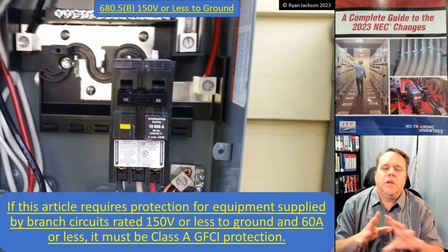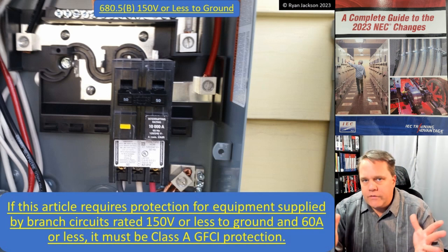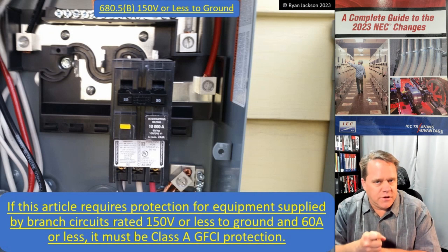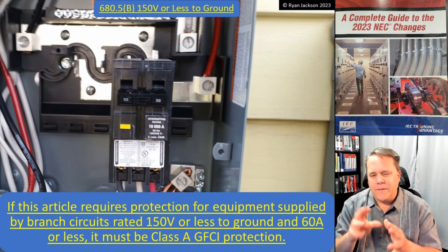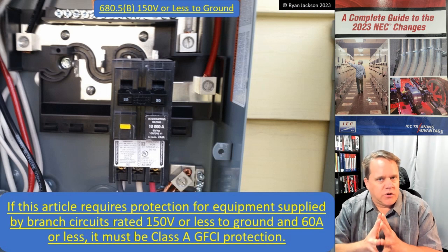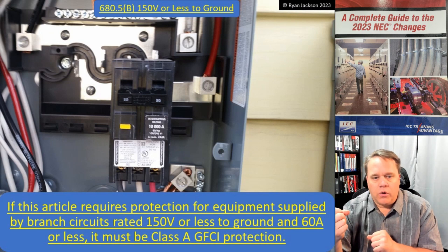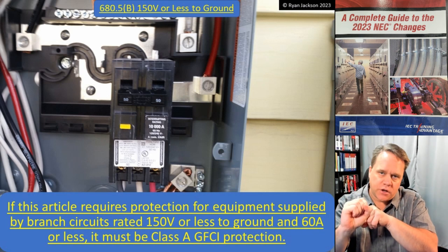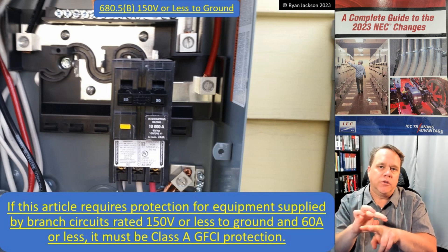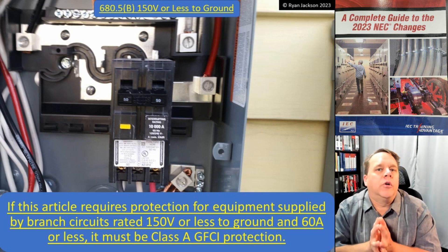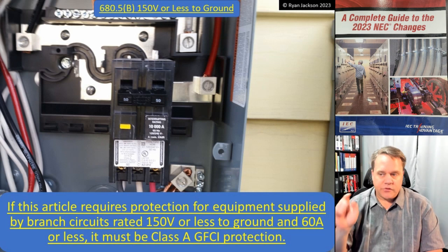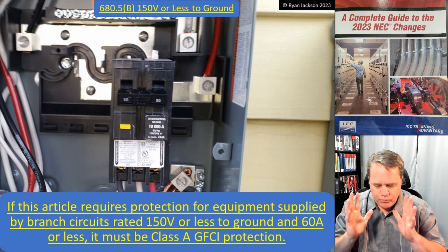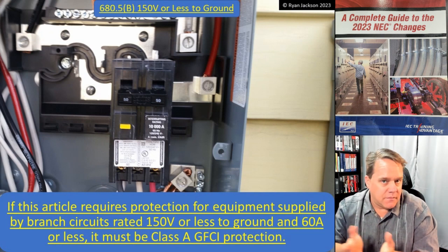GFCIs come in a few different flavors. A Class A GFCI is what we all have in our houses and at commercial buildings. Class A GFCI protection operates between four and six milliamps of leakage current. The way a GFCI works is it measures the current on the circuit conductors — whether that means a hot and a neutral, or two hots, or three hots plus a neutral. It has a CT that wraps around all of the circuit conductors and looks for the same amount of current flowing between them; that number needs to equal zero. If I have a 120-volt load pulling 10 amps, there's 10 amps on the hot and 10 amps on the neutral — the CT wraps around it, recognizes 10 and 10 equals zero, and everything is happy.